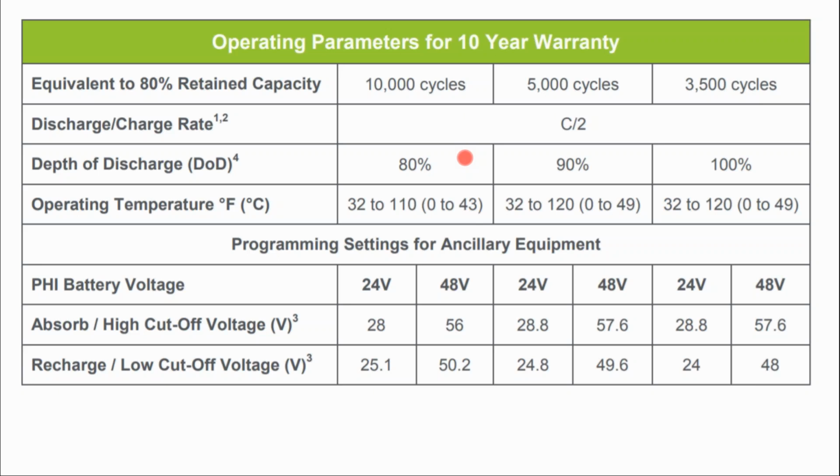And so we don't really care too much about efficiency, but we do want our battery to last as long as it can. So, all I'm trying to say is that even lithium ion has its limitations in terms of dischargeability, and there's even higher quality chemistries that we'll get into that are more favorable for things like rapid discharge. However, it's rare to have a facility that only has a maximum spiky load for 15 minutes. Usually a maximum load might run for an hour, and you would want a 2-hour battery in order to make sure that under worst case scenario, you can still level that load.